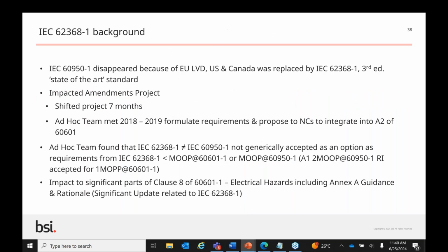And as I promised, I'll talk about 62368 and 60950. So this is information technology equipment primarily. 60950-1 disappeared because of the EU low voltage directive, and US and Canada replaced it by 62368 third edition as the state-of-the-art standard. This happened midway into the amendments project, and it wasn't planned for, it wasn't expected, let's say. And so it was a speed bump within the project. And so we had to come up with an ad hoc team to deal with this sort of midstream. So it definitely gave us a little bit of a glitch.